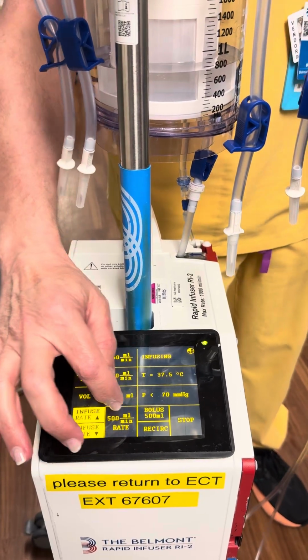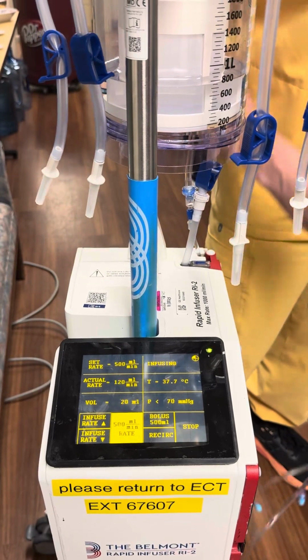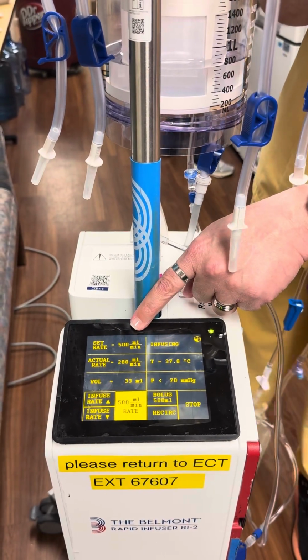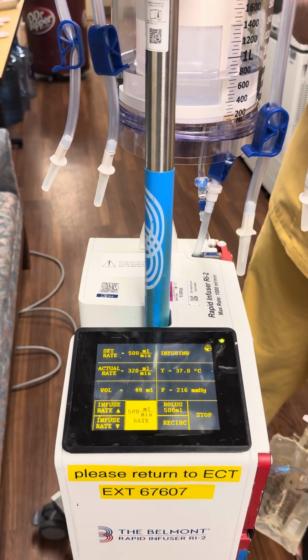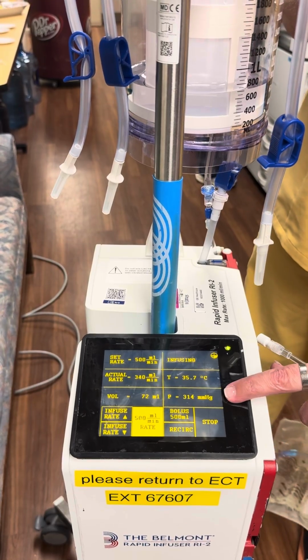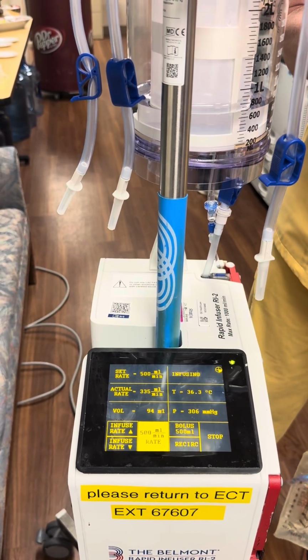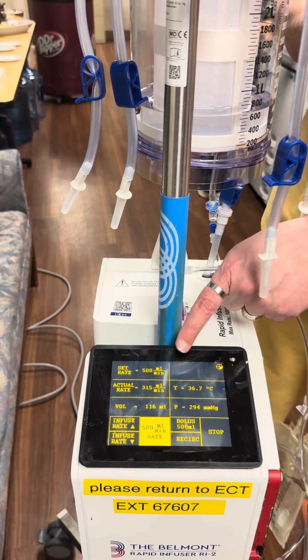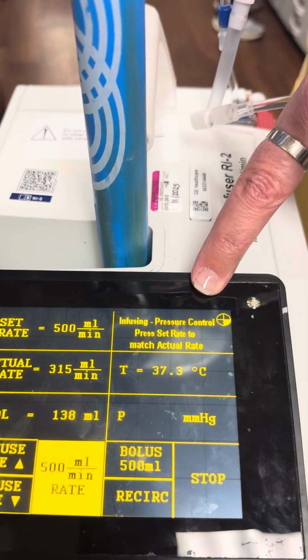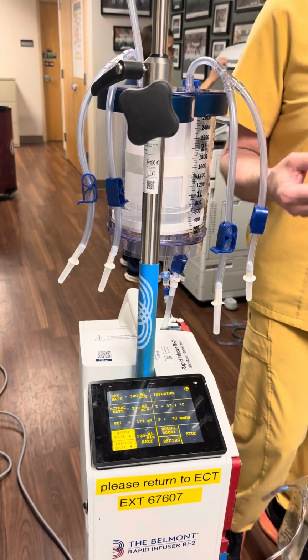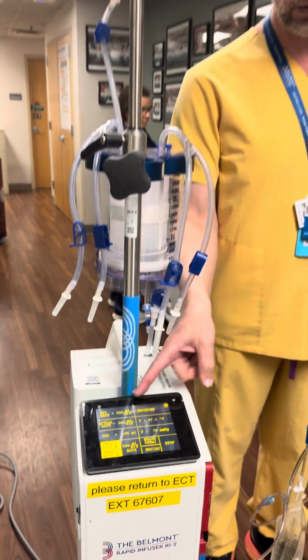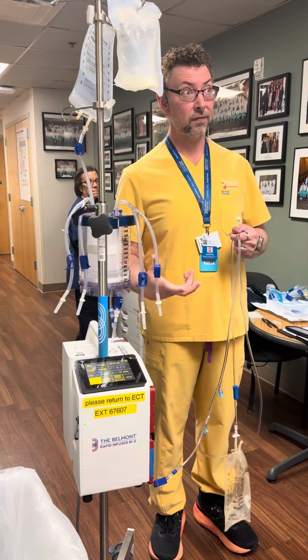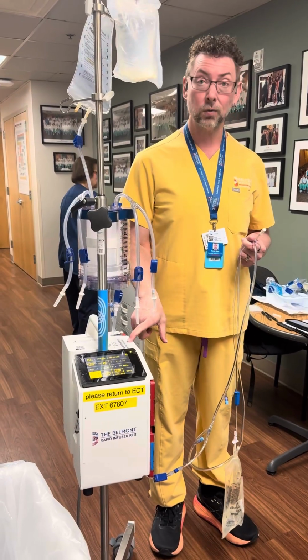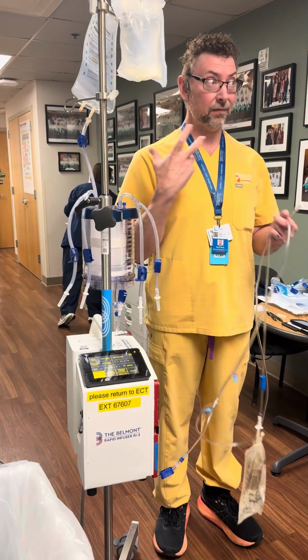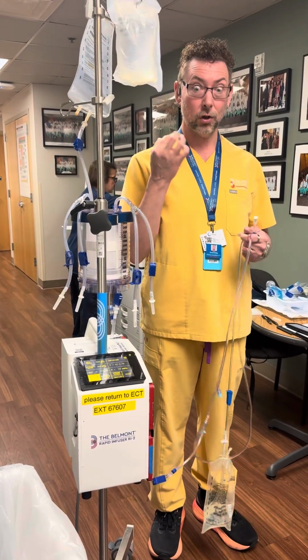Now, if you just need it to go as fast as it can, based on what you're connected to, hit the 500 button and it will try to get you to 500 milliliters a minute. It's going to set the rate to it, try to get you there, but always test the back pressure to make sure you never exceed 300 millimeters of mercury. So if you notice your pressure climbing, the machine will automatically sacrifice the infusion rate. And when it finds the fastest rate it'll give you, keeping the pressure in a safe range, it tells you you're in pressure control. Press set rate to match the actual rate. Touch the word set rate, it matches the two together, and that's as fast as it's going based on the access you're connected to. If you needed to move faster, you got to insert a larger access. Now, if you get it to 300 milliliters a minute, you're giving your patient 18 liters an hour. 750 is going to be 45 liters an hour, and the fastest your machine goes is 1 liter a minute. To get that, you will need the bifurcated line split between 2 9-French catheters or much larger catheters.